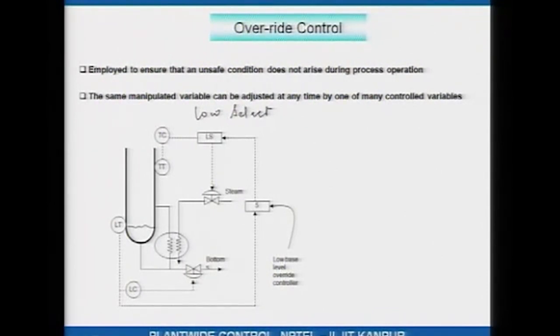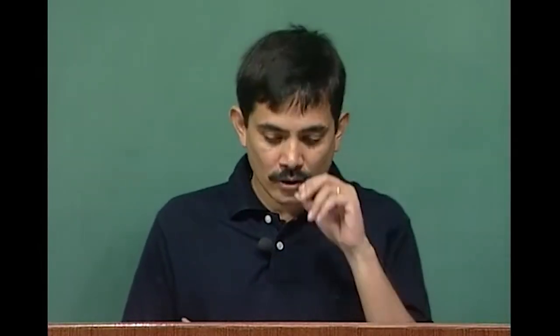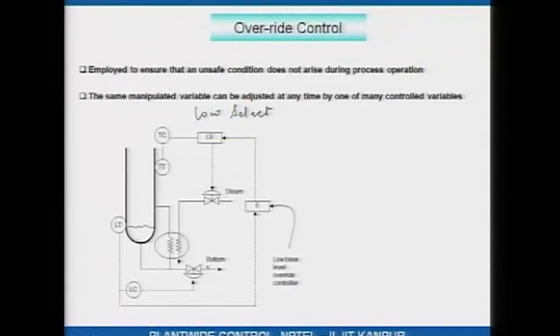Whichever is the lower of the two signals gets passed to the steam valve. On the other side, the level in the bottom sump of the column is controlled using the bottom flow rate. It may happen that the level is reducing, this valve is fully closed, and yet the level still goes on reducing. You would not like the level to go below say 10 percent because then the tubes will get exposed.